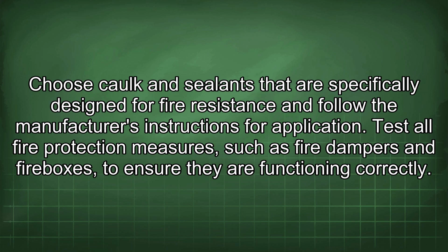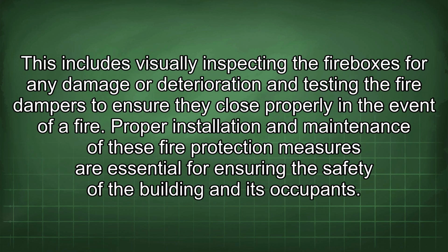Test all fire protection measures, such as fire dampers and fireboxes, to ensure they are functioning correctly. This includes visually inspecting the fireboxes for any damage or deterioration and testing the fire dampers to ensure they close properly in the event of a fire. Proper installation and maintenance of these fire protection measures are essential for ensuring the safety of the building and its occupants.